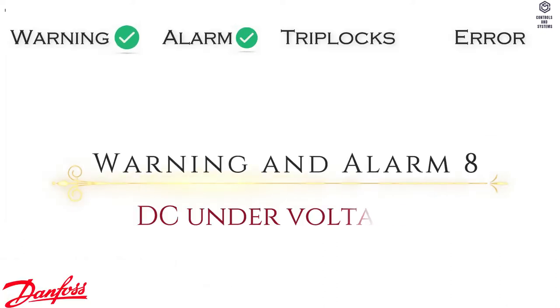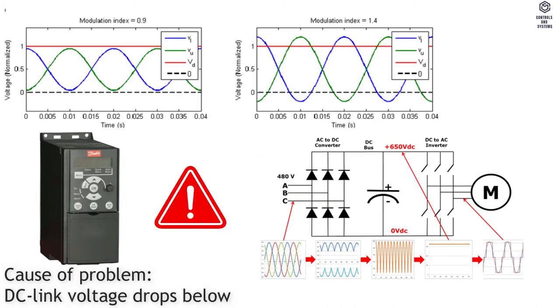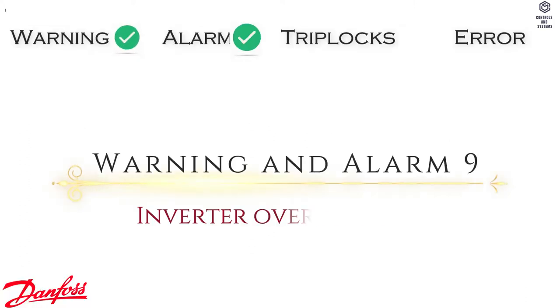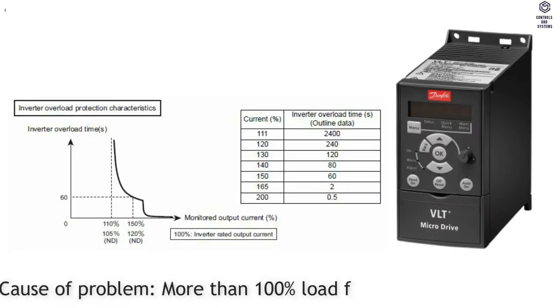Warning and Alarm 8: DC Undervoltage. Cause of Problem — DC link voltage drops below the voltage warning limit. Warning and Alarm 9: Inverter Overloaded. Cause of Problem — more than 100% load for too long.